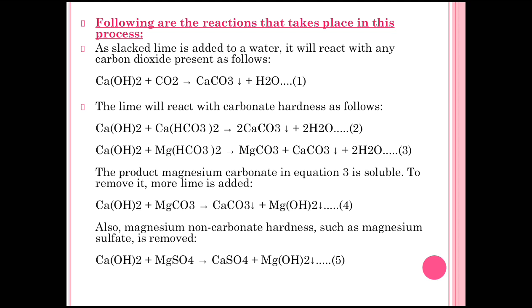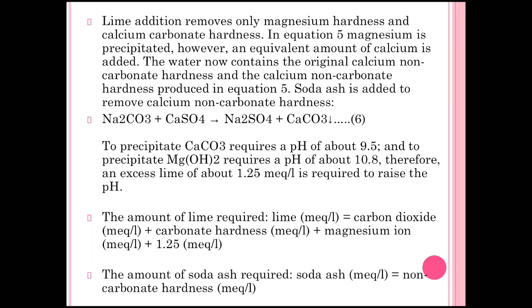Magnesium non-carbonate hardness such as magnesium sulfate is also removed — when lime reacts with water containing magnesium sulfate, calcium sulfate and magnesium hydroxide precipitates are removed. When lime addition removes only magnesium hardness and calcium carbonate hardness, an equivalent amount of calcium is added back to the water, which then contains the original calcium non-carbonate hardness plus calcium non-carbonate hardness produced in reaction 5.